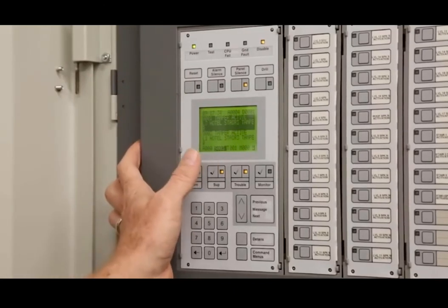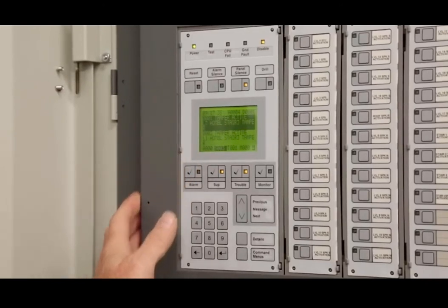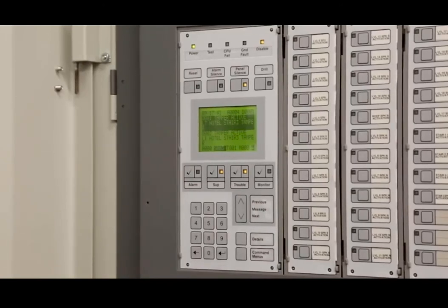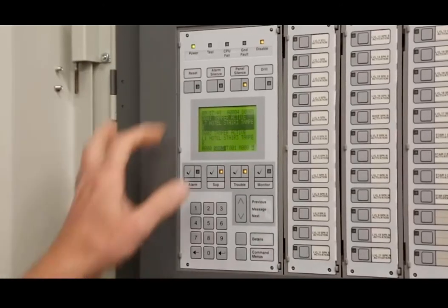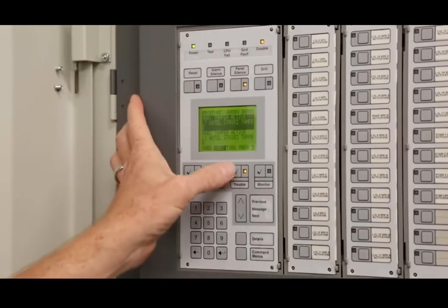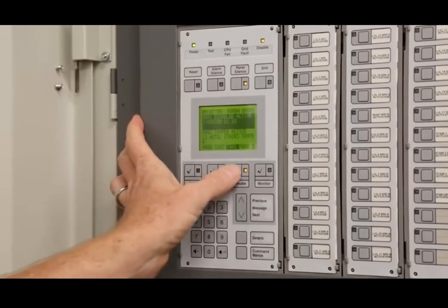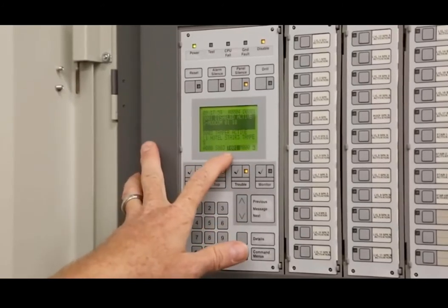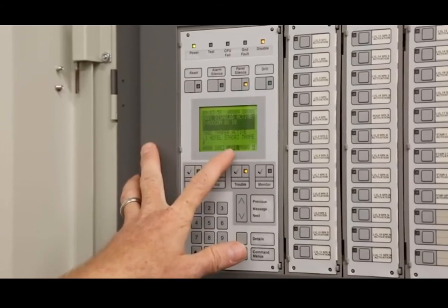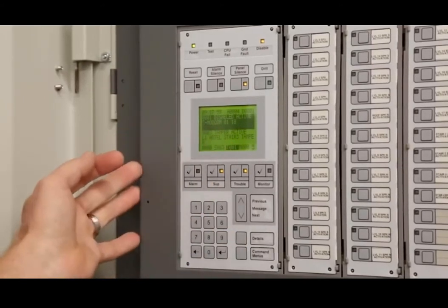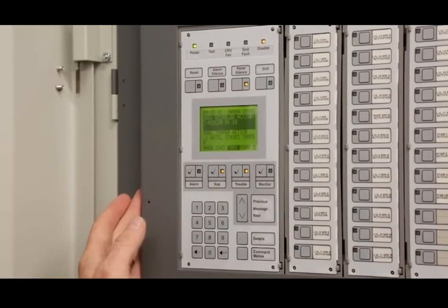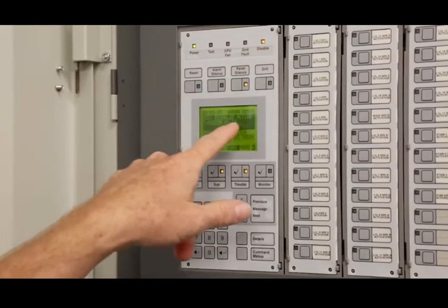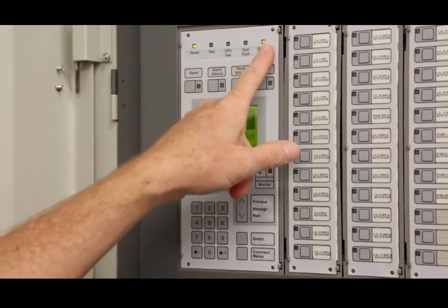Troubles would be any abnormal condition, and it could be that the device is not responding, could be an open circuit, or it could be like we have right now, disabled. For instance, you can pull up your troubles by just hitting the button right there, and you can scroll up and down. If you see there's a T right there that represents troubles, there's only one. Right now it says No Com. That's because I have the dialer offline, so it won't report right now. And also, if we have anything disabled, like I have this disabled, it says disable active, your disable light's on up here, okay?